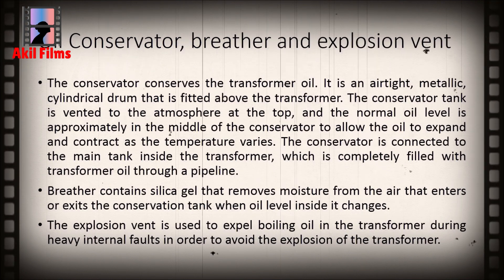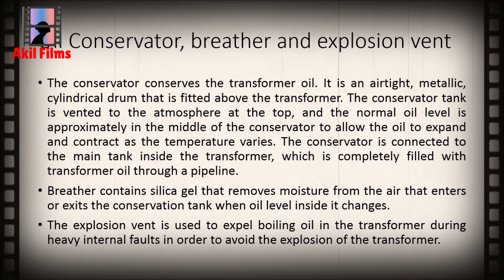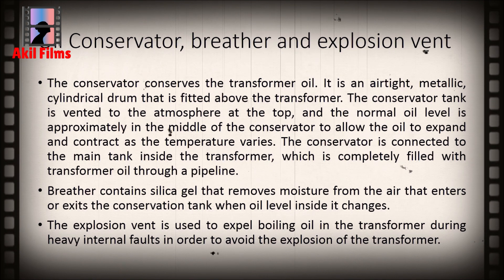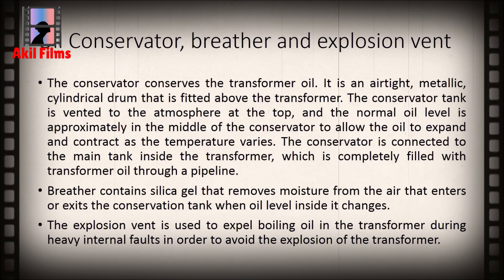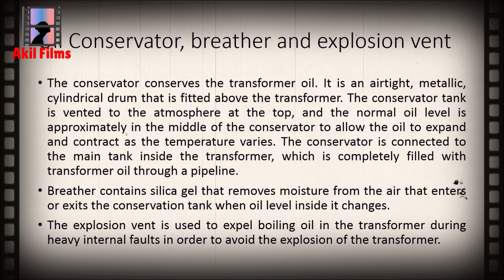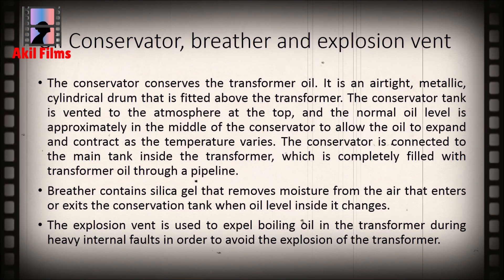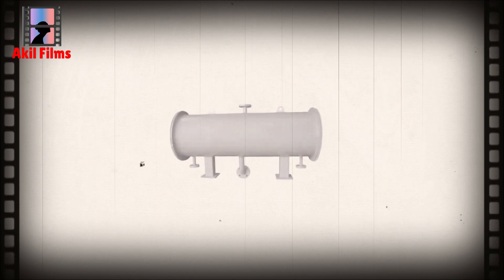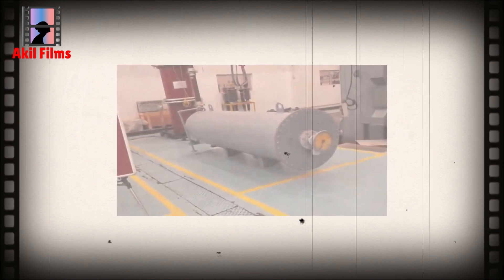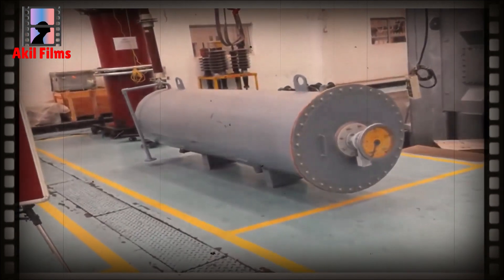The conservator conserves the transformer oil. It is an airtight, metallic, cylindrical drum that is fitted above the transformer. The conservator tank is vented to the atmosphere at the top, and the normal oil level is approximately in the middle of the conservator to allow the oil to expand and contract as the temperature varies. The conservator is connected to the main tank inside the transformer, which is completely filled with transformer oil through a pipeline.